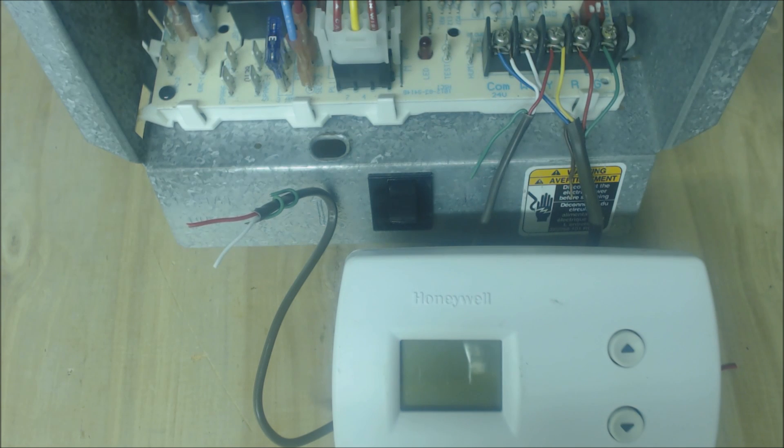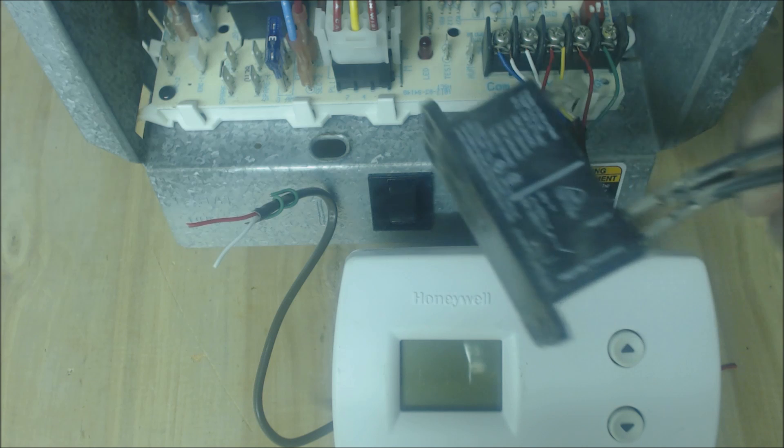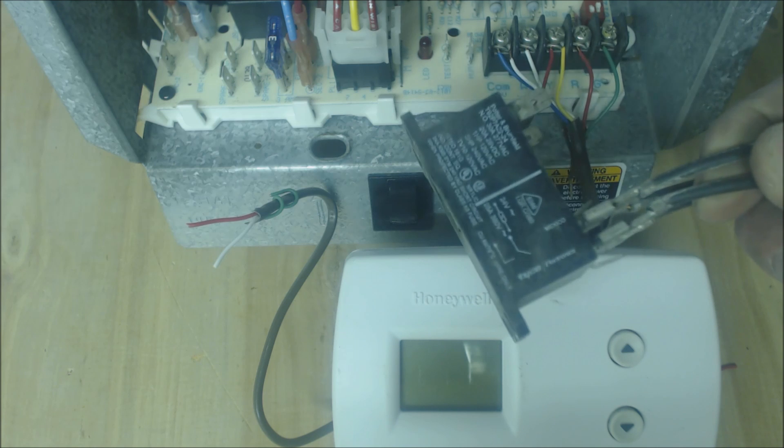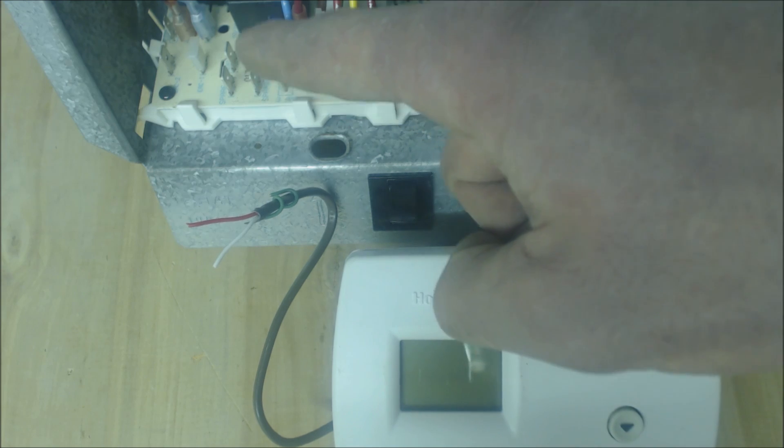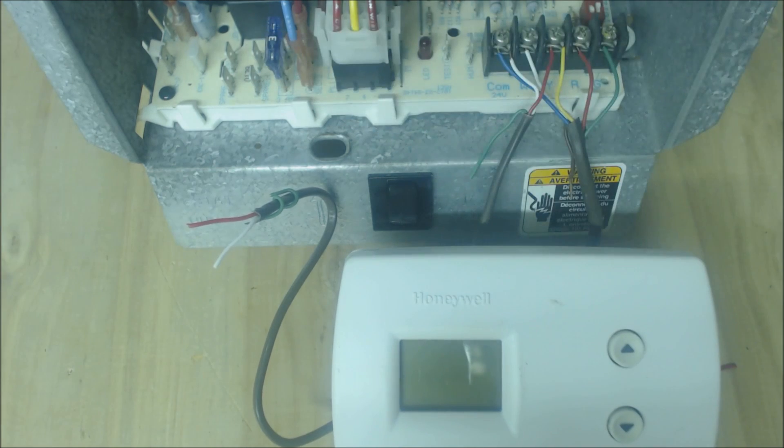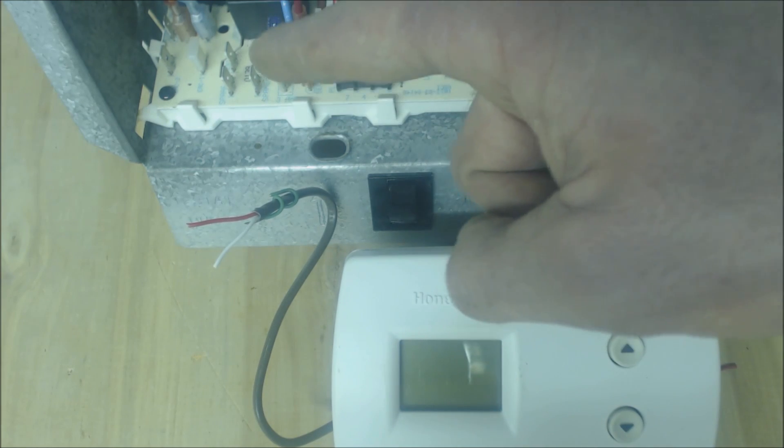Another thing is that maybe you have too many field applied relays and you're drawing too much amperage, and it's adding up to over 3 amps and that's why it's popping.